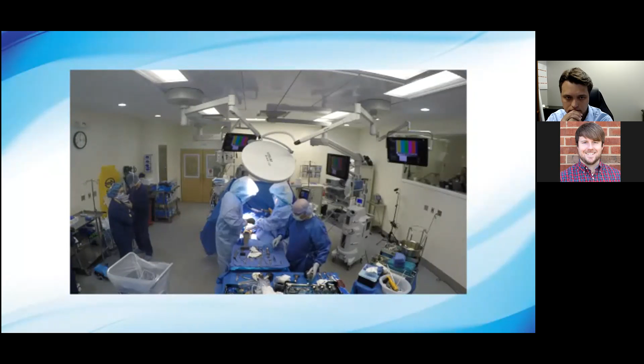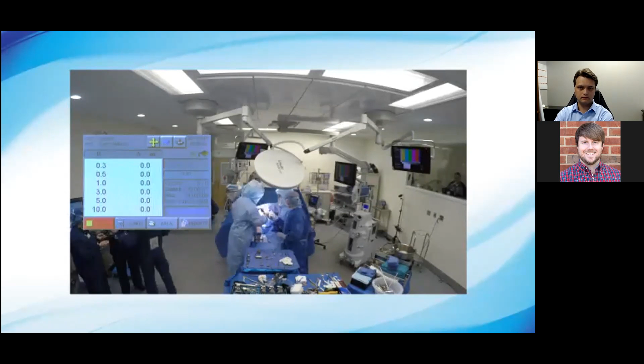In all current ORs, laminar flow actually draws particle-laden air from the perimeter of the room and delivers it directly over the patient. Even with the best filtration available, the operative field is continuously flooded with contaminants. To solve this problem, Precision Air created Surgic Air Zero, the first and only system to achieve and maintain zero particles in the operative field. Surgic Air Zero is a comprehensive air control system that can protect the patient from both activity in the perimeter and contaminants generated by staff near the table, as demonstrated by this real-time particle count during surgery. While particles and bacteria are continuously shed by everyone in the room, none of them reach the patient.